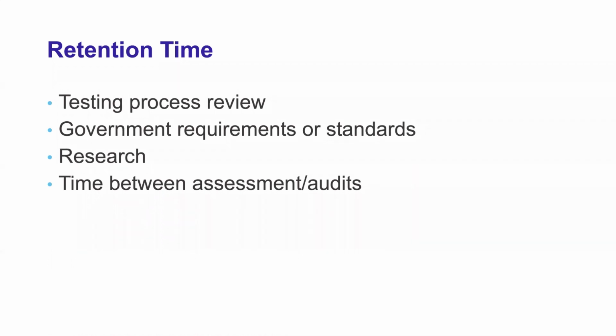The length of time that you keep the records may vary based on how long you need to access them. So you say, okay, we're going to review a year's worth of Levey-Jennings plots. Then you want to keep your Levey-Jennings plots for a year. So decide how long ago you want to do your retrospective review, and then decide your retention time accordingly.